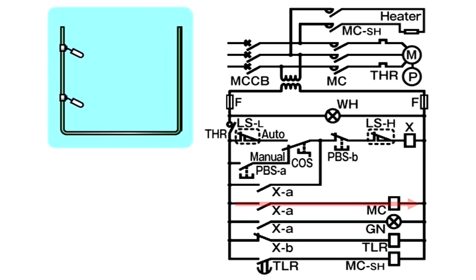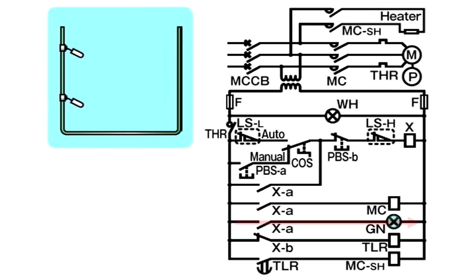When X-A is turned on, the coil of MC is excited. As MC's coil is excited, MC's contactor is turned on. Current is passed to the motor through MCCB, MC, and THR, and the motor starts. Then the pump starts operating to supply the tank with fuel oil. As X-A is turned on, the green operation lamp illuminates.